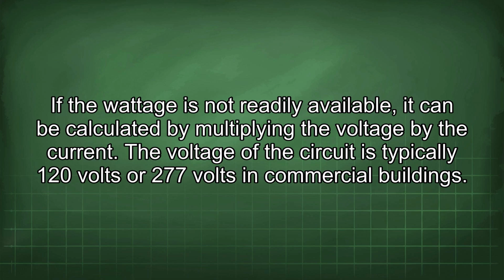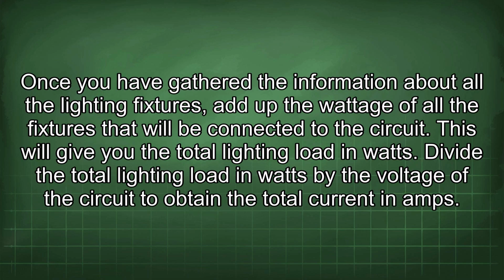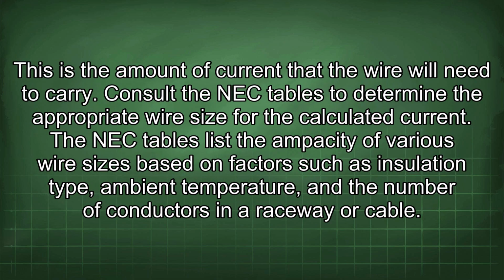The voltage of the circuit is typically 120 volts or 277 volts in commercial buildings. Once you have gathered the information about all the lighting fixtures, add up the wattage of all the fixtures that will be connected to the circuit. This will give you the total lighting load in watts. Divide the total lighting load in watts by the voltage of the circuit to obtain the total current in amps. This is the amount of current the wire will need to carry.